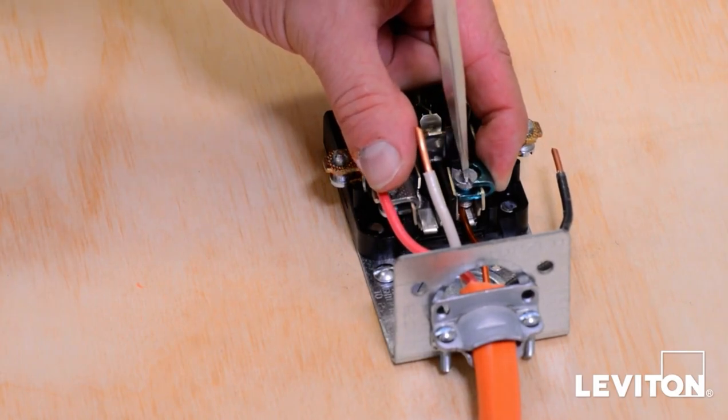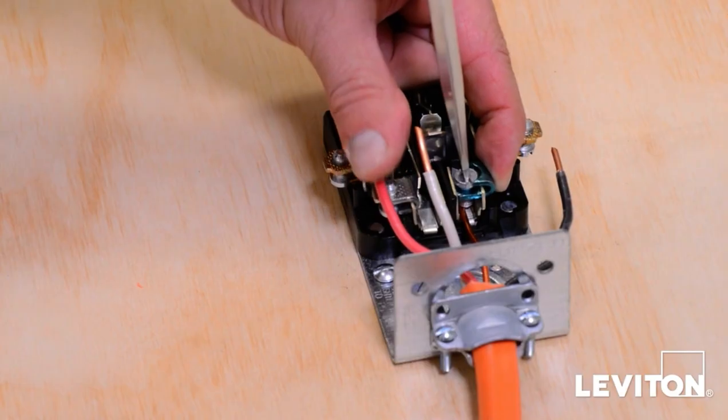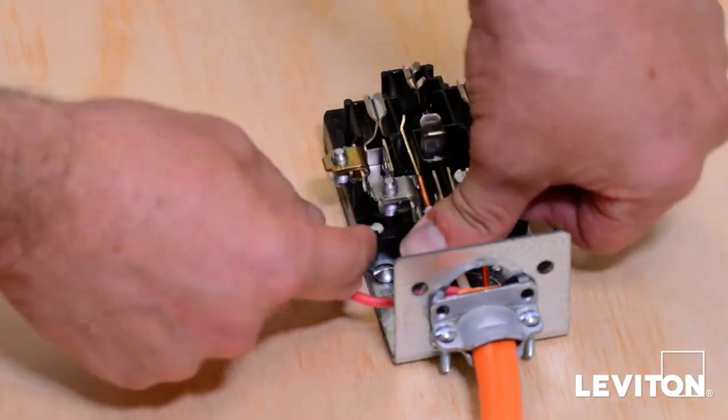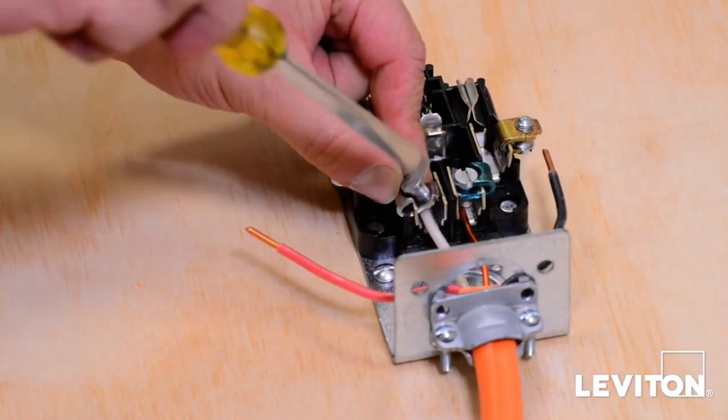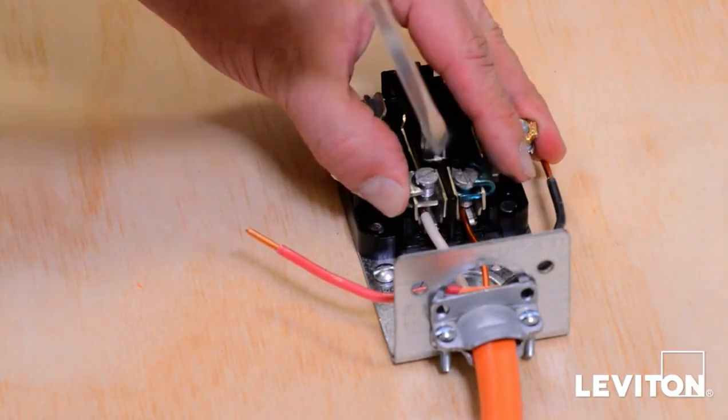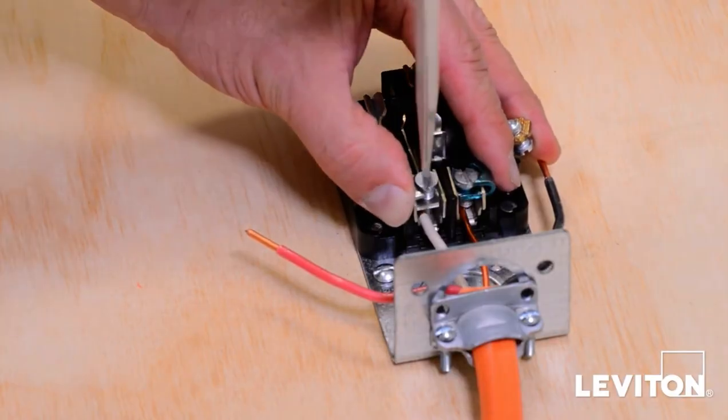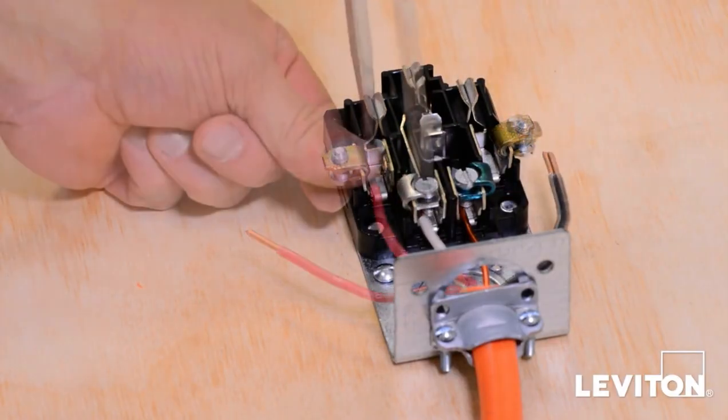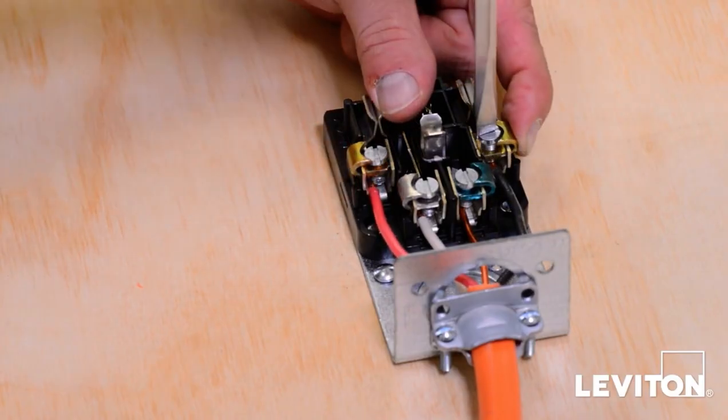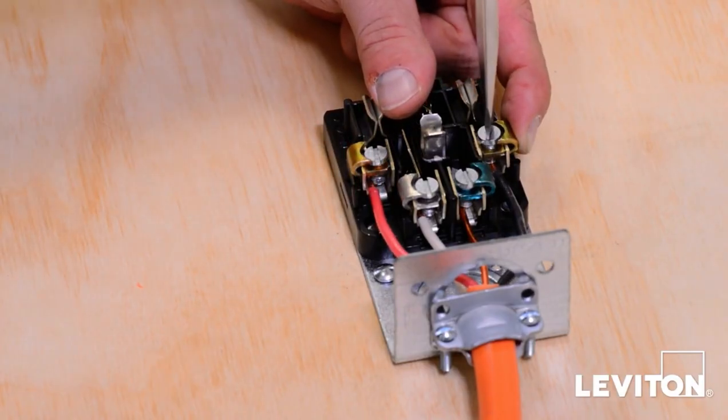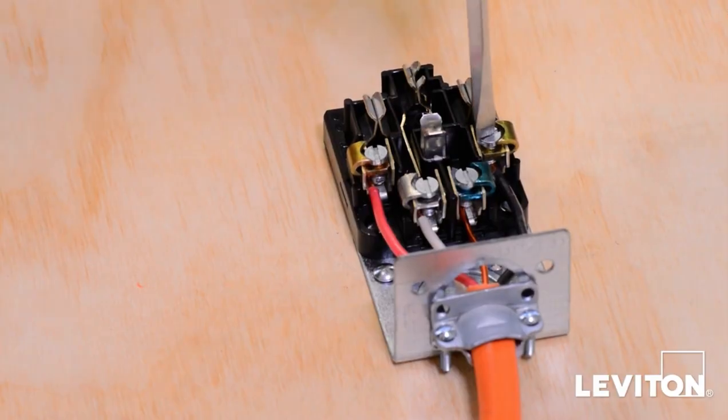Insert the ground wire under the green screw, the white neutral wire under the silver screw, and the remaining hot wires under the brass terminals. Tighten terminal screws to 25 inch pounds.